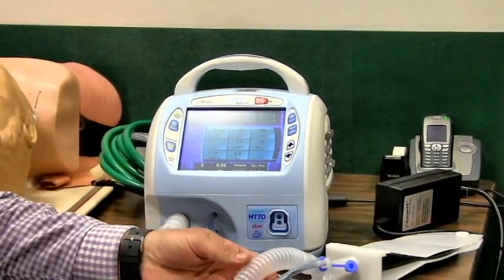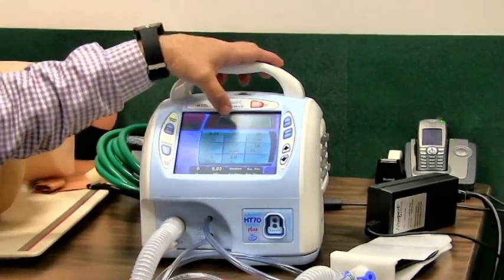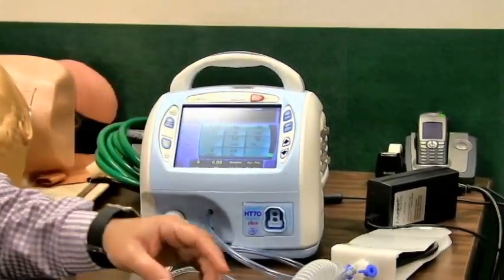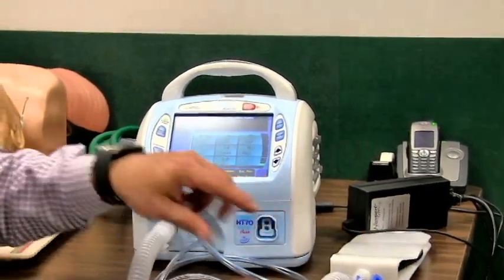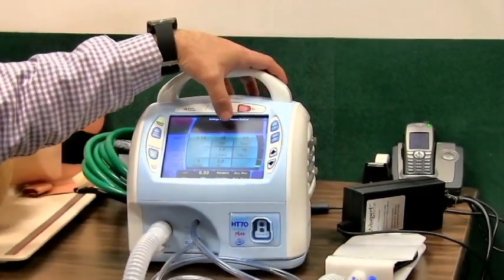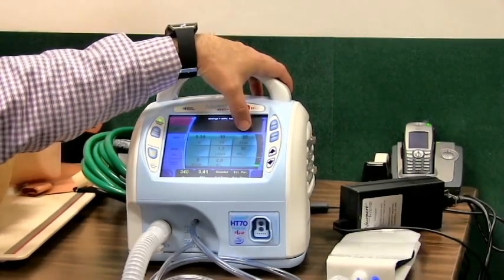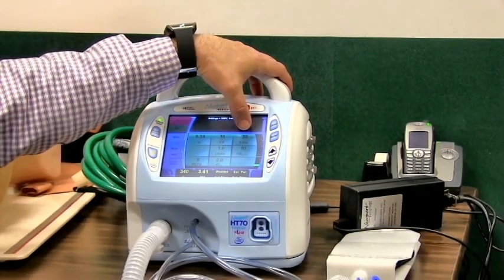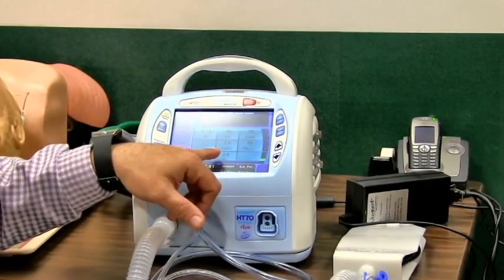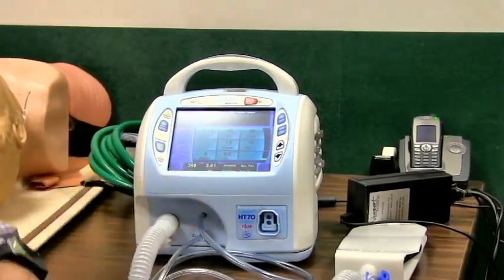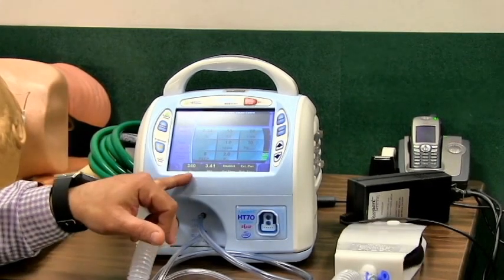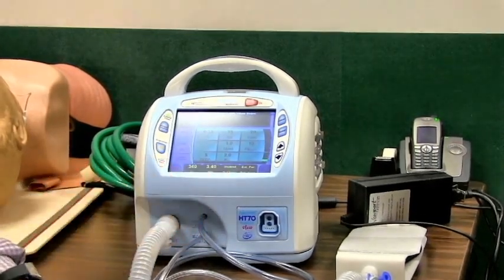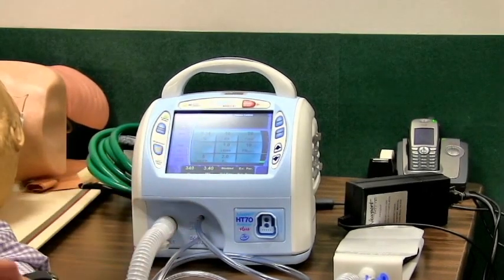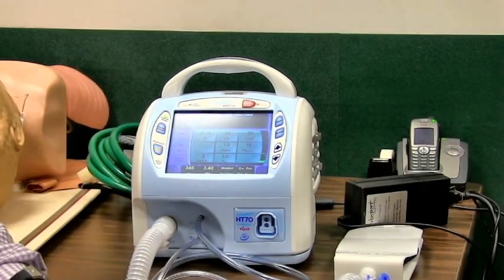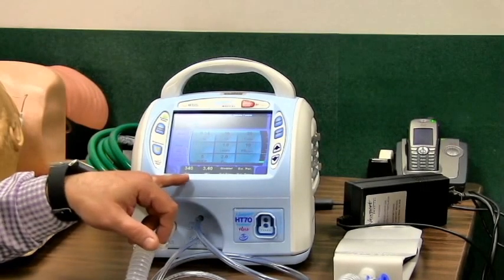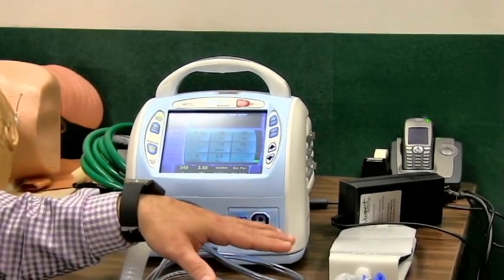Now I'm just going to initiate the start ventilation. And when I start ventilation, it's going to deliver the patient breaths at 340 cc's of air per breath, 10 breaths per minute. My flow is set by the machine based upon the volume that we put in, and it's at 20. It's going to deliver it over 1 second for our I time. Pressure support is 10 if the patient takes their own breath. Our PEEP right now is 5 and our pressure trigger is 2. Again, the pressure trigger and pressure support are not needed unless the patient attempts to interact with the ventilator with their own breath.